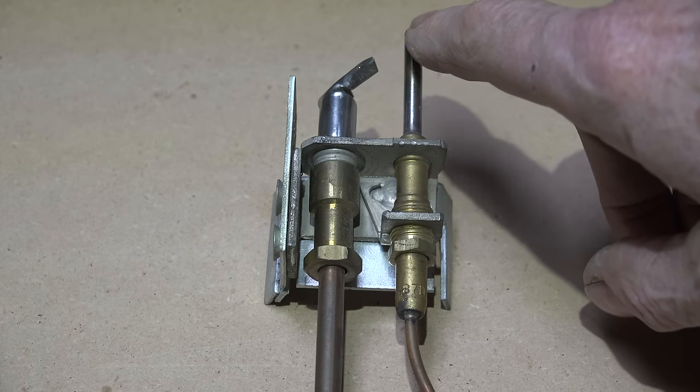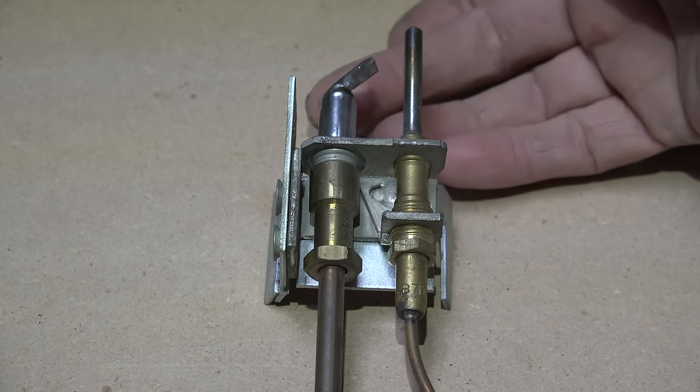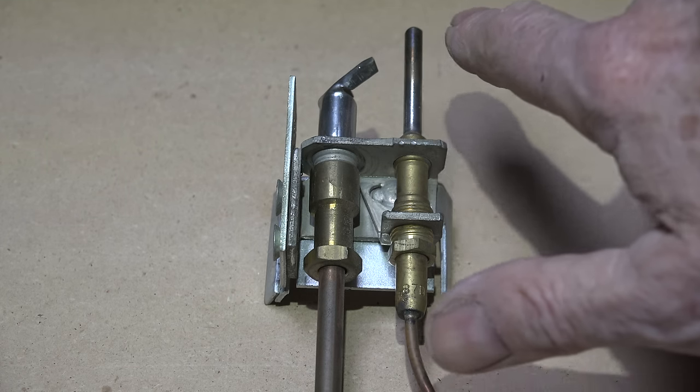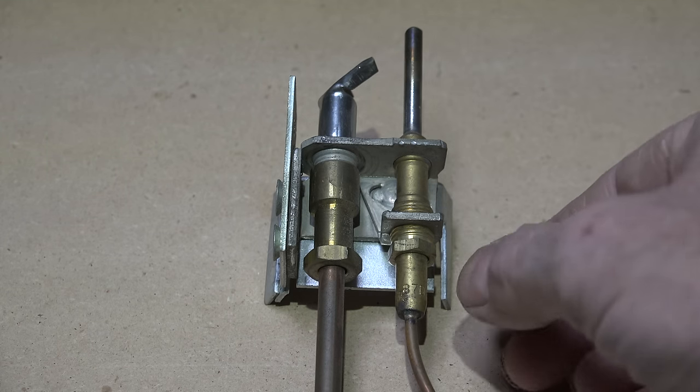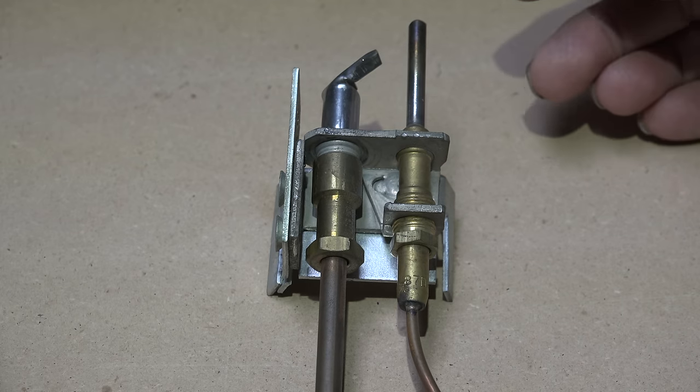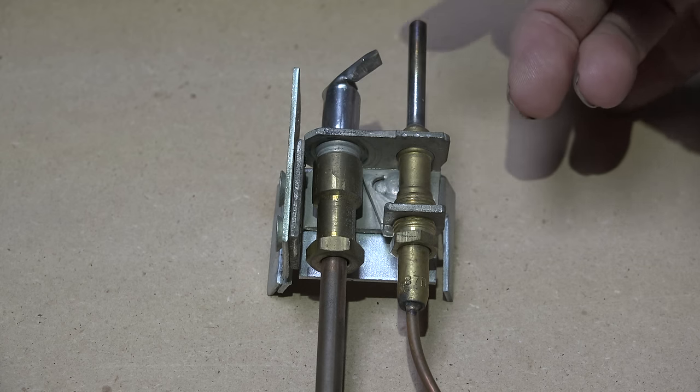It lights a burner with this part here, so this flame should be covering about 3/8 of an inch. This unscrews - you can unscrew this thing and pull it out. When it's put in there, it should be about that kind of height so that this covers at least 3/8 of an inch of the thermocouple when it's burning.